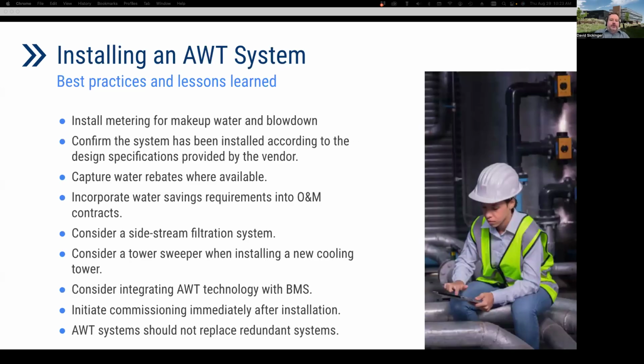And then installing some of these are best practices and lessons learned when installing an AWT system. You'll want to install metering for the makeup water and blowdown water. Good time to consider replacing with new meters if you have existing hardware that is a few years old, so that you can have confidence in the data. Confirm the system has been installed according to the design specifications provided by the vendor. GSA found several AWT installations with minimum water flow and drain capacity needs that were not initially met, which compromise the overall system performance.